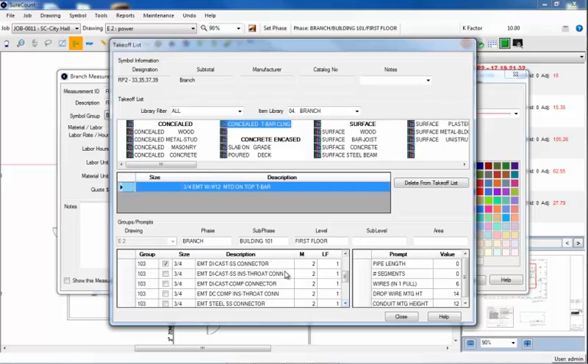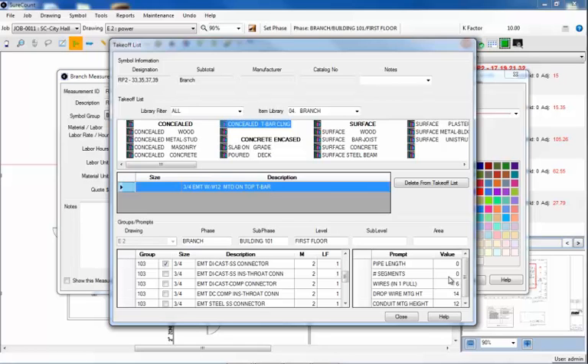There are various pipe sizes. I'll select 3 quarter inch EMT, filled with number 12 wire, mounted on top of T-Bar. There's the assembly, and below are the pre-selected couplings and connectors. On the right, the prompts seem to be missing a couple of values. Pipe Length. Well, I'll measure that run in a minute, and when I'm finished with the measurement, Sure Count will place that final number right here for me. The other prompt is for the number of segments. Every time I add a segment to a particular pipe run, Sure Count will add 2 extra connectors to the run at this prompt. I don't know how many segments I may need in this run, if I need any at all, so we'll leave that one at 0 as well. I'm finished with the takeoff, so I'll click the Close button.